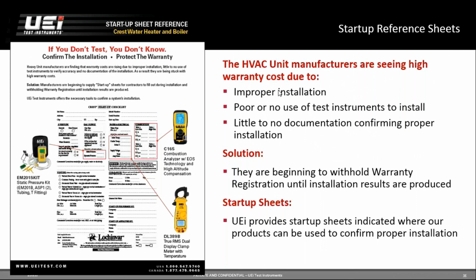No longer are we in the day where you install the boiler, look at the flame, think it looks right, something goes awry, and you call the manufacturer saying this isn't right, I want to claim warranty. They're going to ask first: what was the gas pressure? And they're not going to accept 'it's right'—they want actual values.